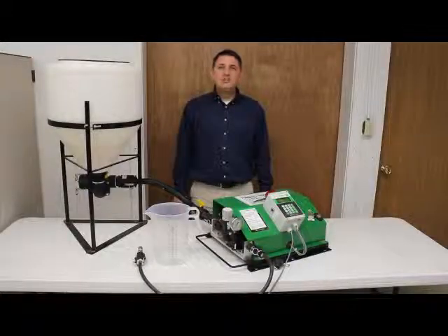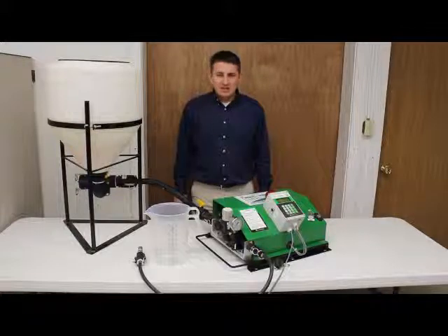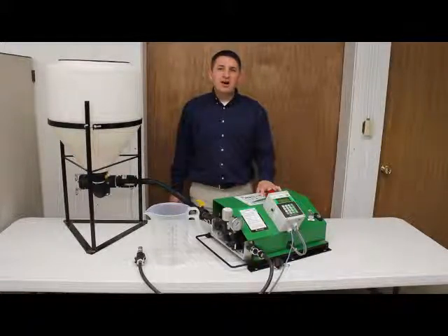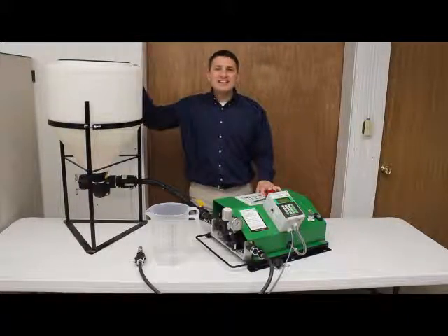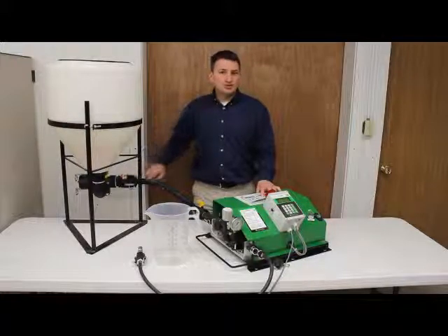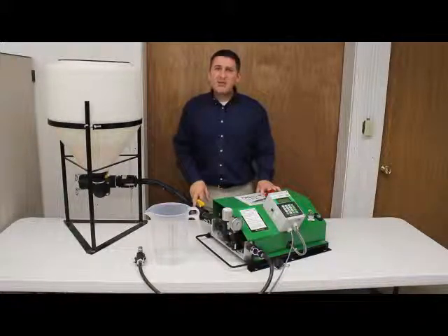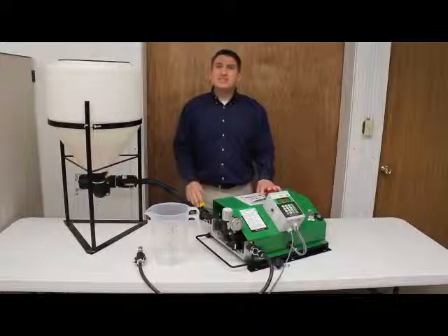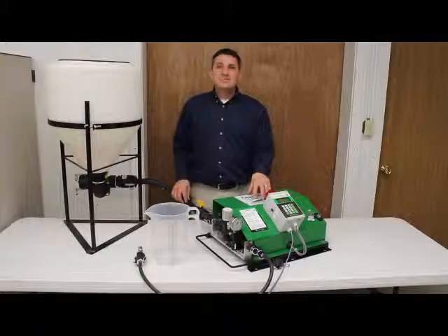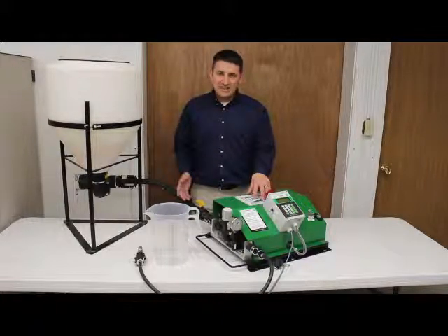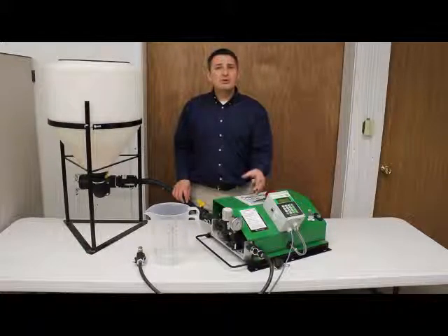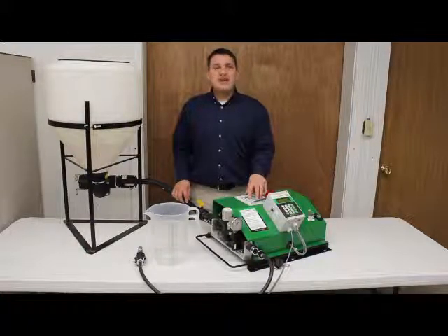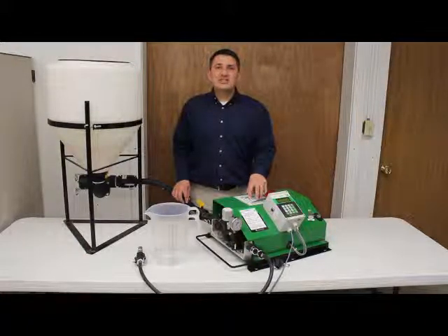The first step is we want to discuss proper InjectMATE setup. By doing this, we want to position the pump so it's lower than the actual product tank, allowing the product to naturally gravity feed the pump, also known as a flooded suction. In addition to proper plumbing setup, we also need to have proper power setup. Please verify that you have proper 12-volt connections and battery terminals are clean.